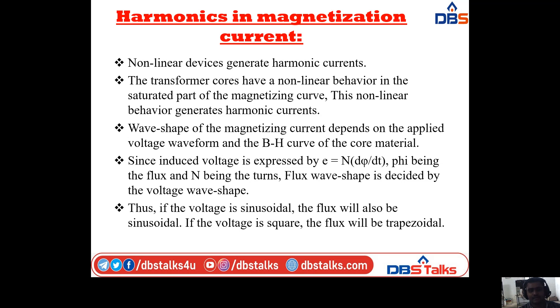The harmonic currents are generated by non-linear devices. The transformer has a non-linear behavior in the saturated part of the magnetizing curve. This non-linear behavior generates harmonic currents. The wave shape of the magnetizing current depends on the applied voltage waveform and the BH curve of the core material.